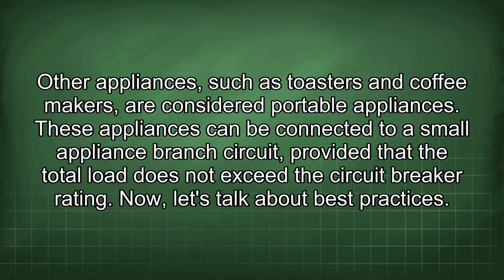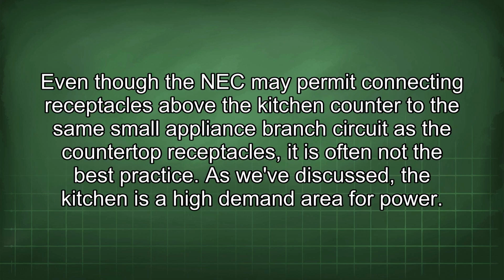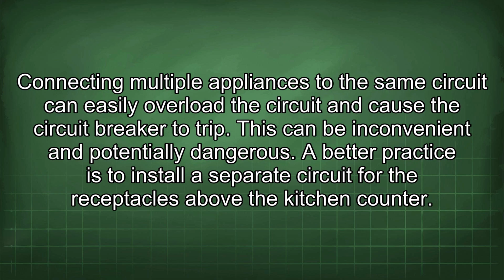These appliances can be connected to a small appliance branch circuit provided that the total load does not exceed the circuit breaker rating. Now let's talk about best practices. Even though the NEC may permit connecting receptacles above the kitchen counter to the same small appliance branch circuit as the countertop receptacles, it is often not the best practice. As we've discussed, the kitchen is a high-demand area for power. Connecting multiple appliances to the same circuit can easily overload the circuit and cause the circuit breaker to trip. This can be inconvenient and potentially dangerous.